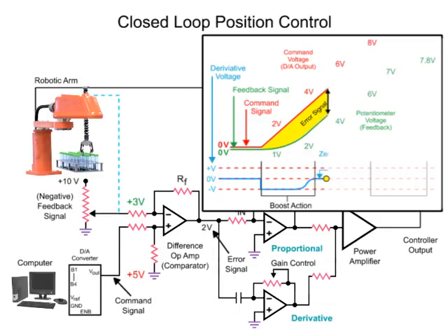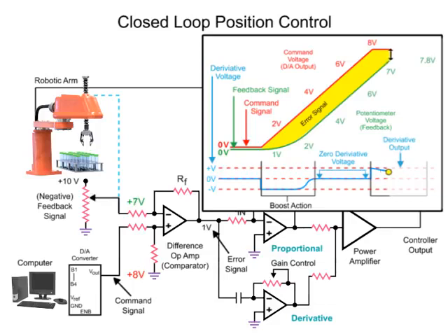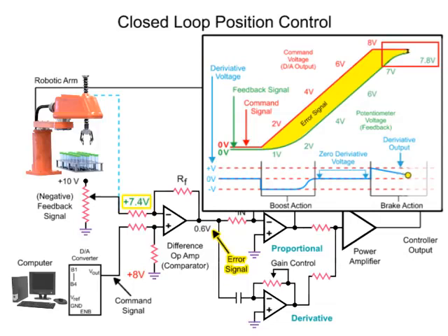As the command signal stops changing, the robotic arm continues to move with a decreasing error signal. As the error is reduced, the derivative amplifier output voltage changes polarity and cancels the proportional voltage. When this occurs, the polarity of the power amp is reversed, creating a brake condition to prevent overshooting the desired position. As the arm continues in motion, the feedback voltage nears the command voltage, the error signal from the difference op-amp decreases, and the arm motor speed decreases.